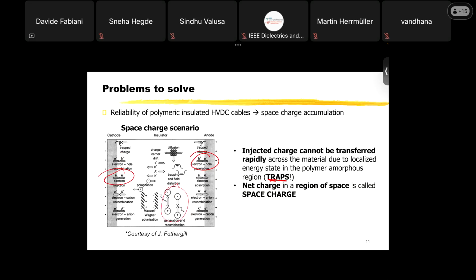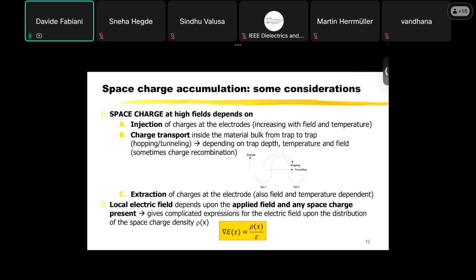This space charge becomes quite important at high fields because the injection of charge at the electrodes, the negative charge coming from the cathode and the positive charge from the anode, increases with the field and the temperature also. So by increasing field and temperature, you can have a lot of charge injected in your material. We have then another mechanism, which is the charge transport inside the material bulk. And this charge transport occurs from one trap to another trap.